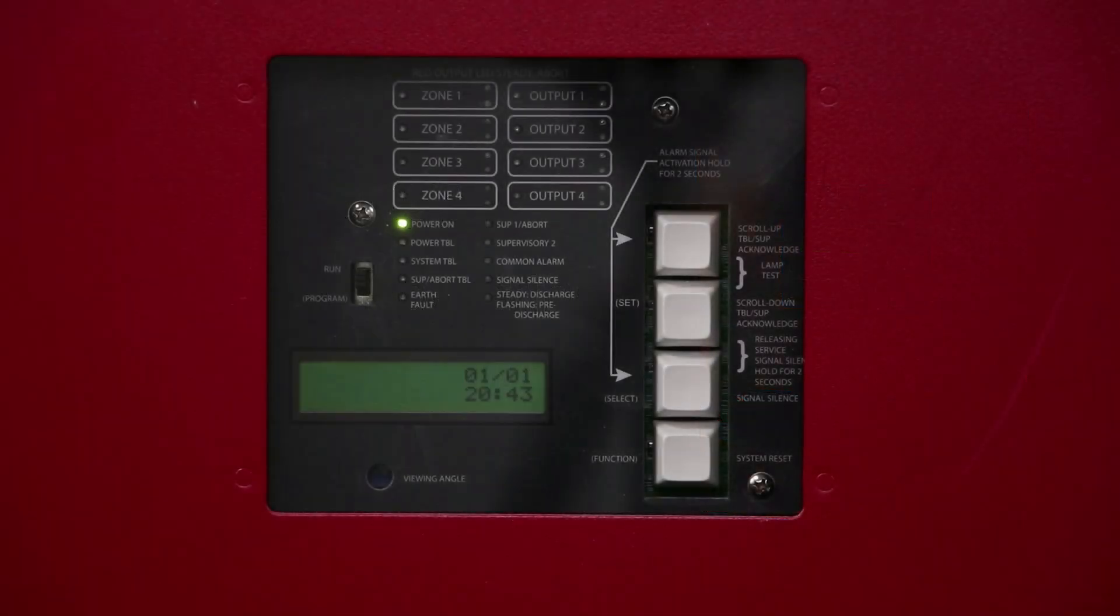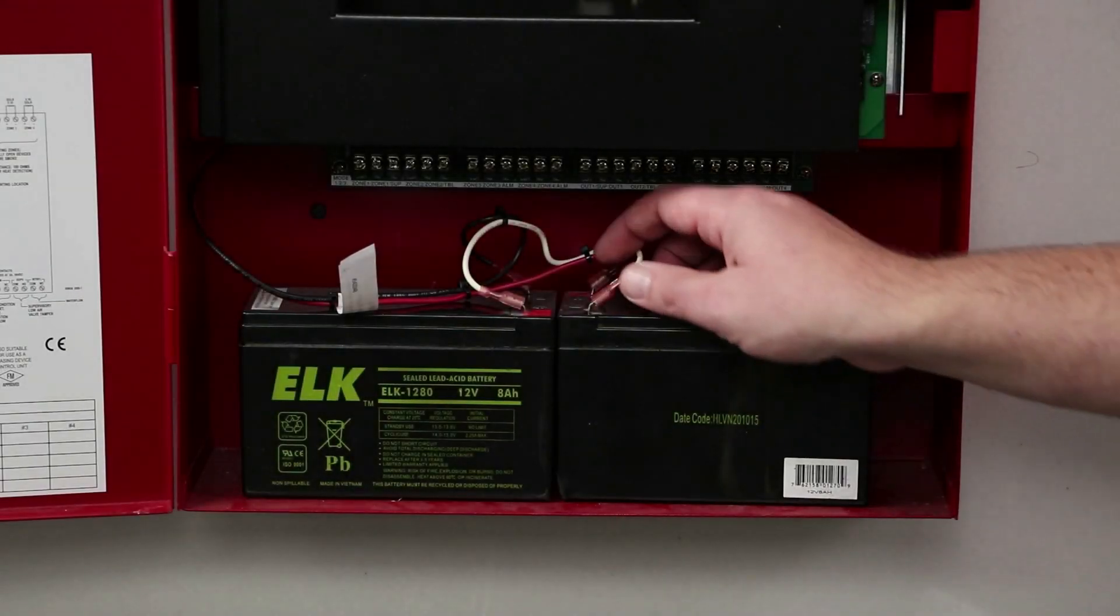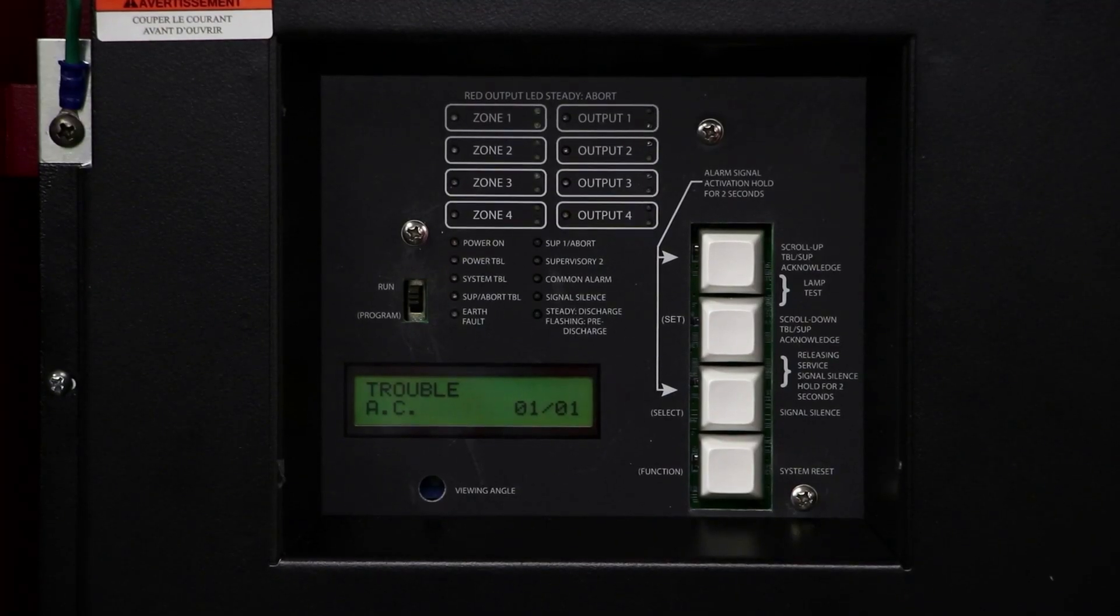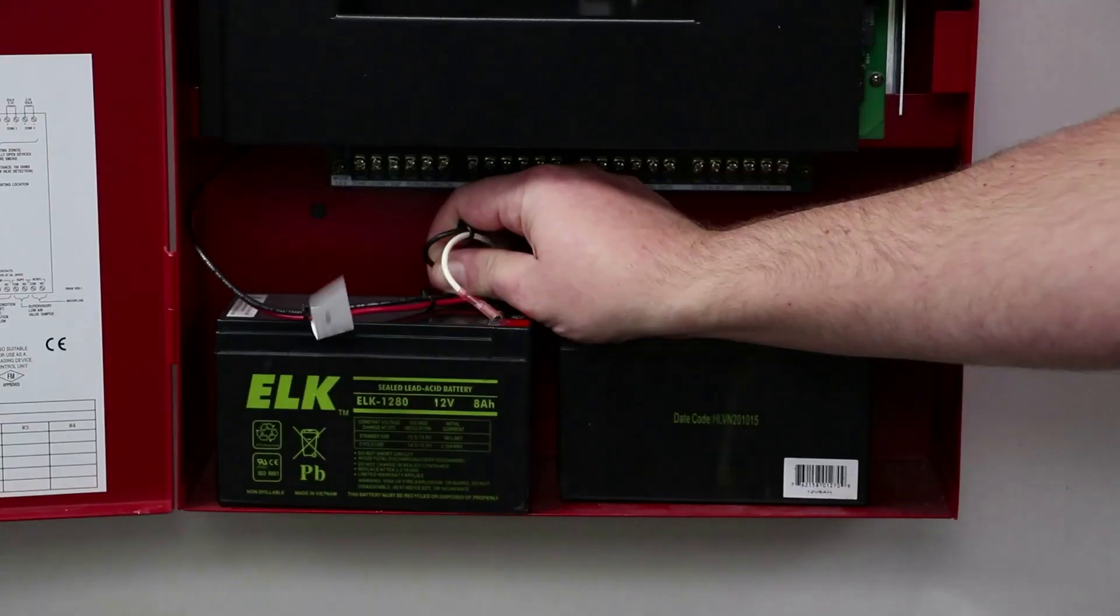In order to replace a PFC 4410 RC with the new PFC 4410 G3, first shut off the main AC power at the circuit breaker. The AC trouble light will illuminate. To fully power down the panel, disconnect the batteries and remove them from the enclosure and set aside.